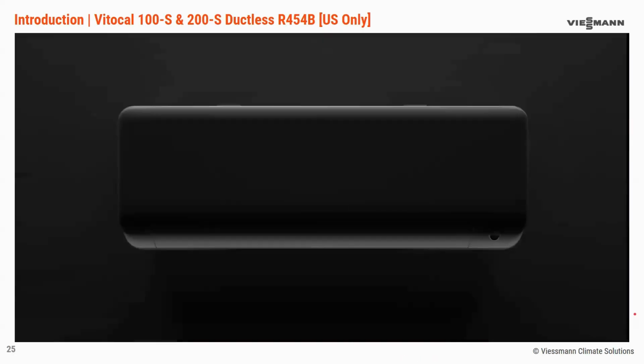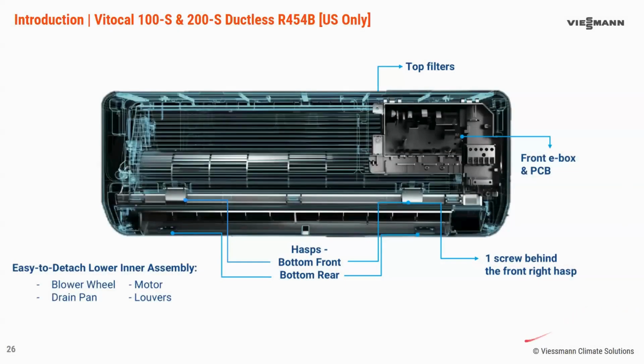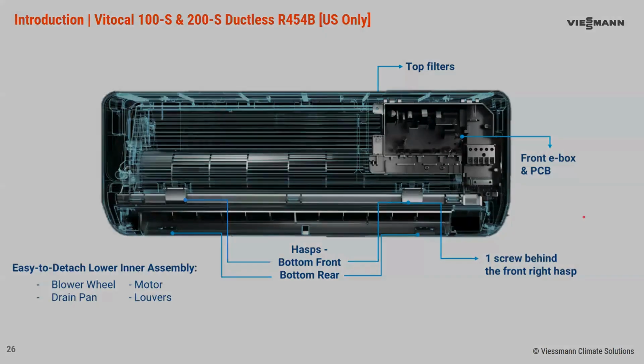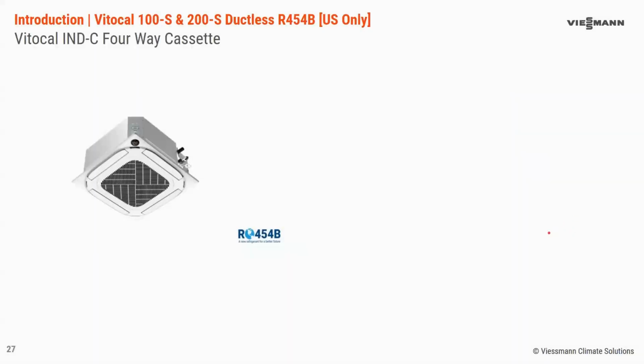That gives you access to the blower wheel, blower motor, the drain pan, the louvers, and the louver motor. It's really great, especially if you're trying to clean the blower wheel. You don't have to clean it in place, potentially creating a mess in the space. And the electronics are front and center here, easy to access. So the high wall is really optimized for longevity, for maintenance and service. That's the big call out on the high wall.